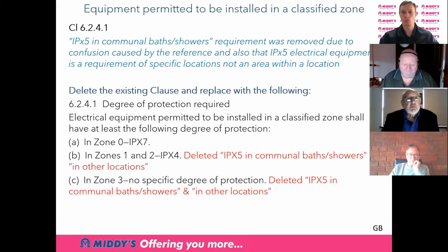Yes, this is an interesting one, Roy. It's really just catching up with some old terminologies and trying to make it a bit clearer about areas of communal baths and showers. We all know sports clubs have them, change rooms, they're community or communal, used by a number of people. And there was an IPX5 requirement for the equipment that went into communal baths and showers. The confusion was caused by that reference because it tended to say it's the whole area. And actually, it's about the zones within the area, not the whole communal bath or shower area. It's about those zones: zone 0, zone 1, zone 2, zone 3, and so on.